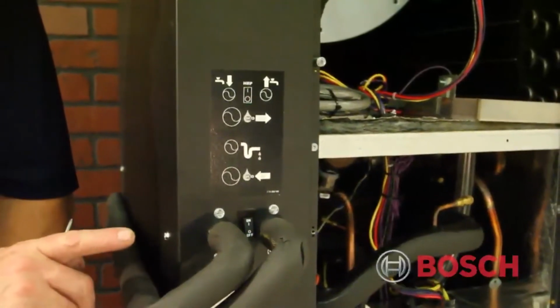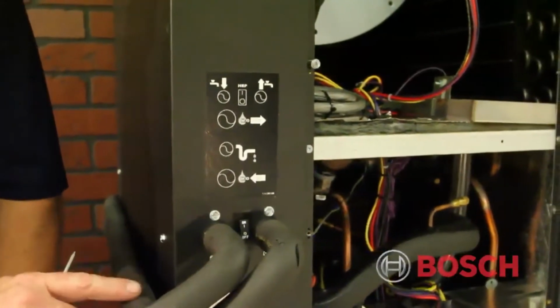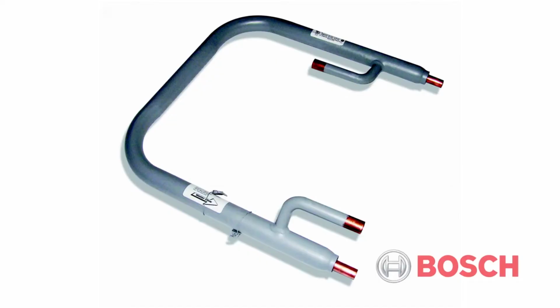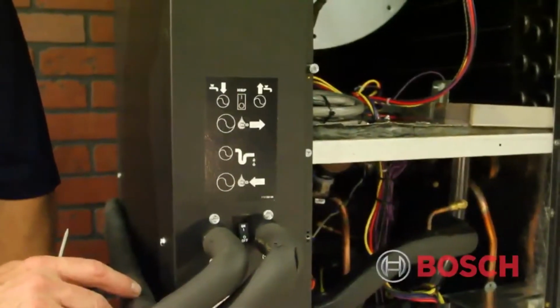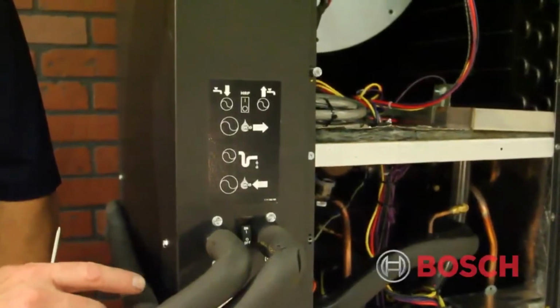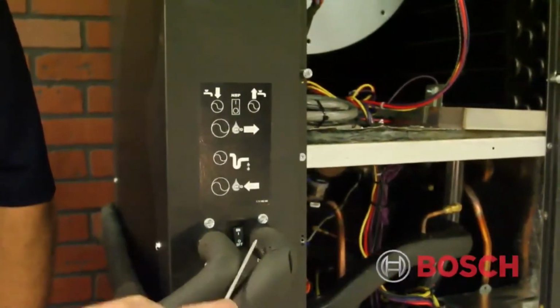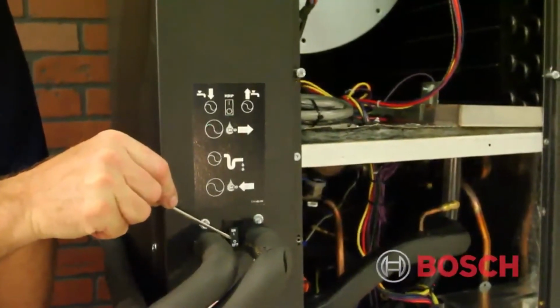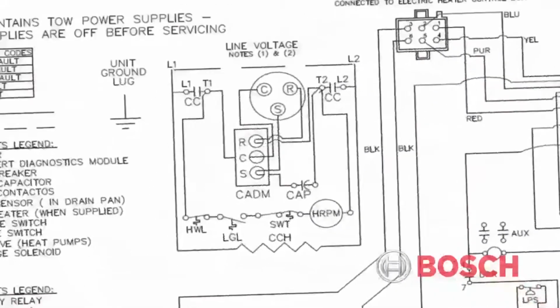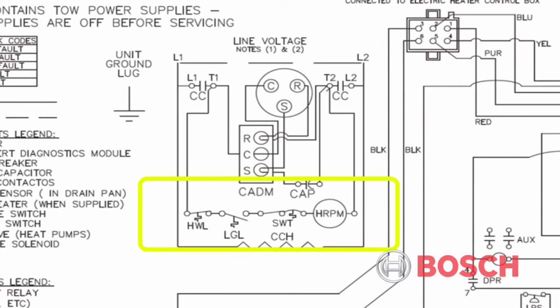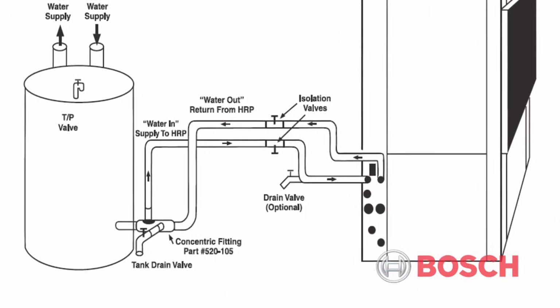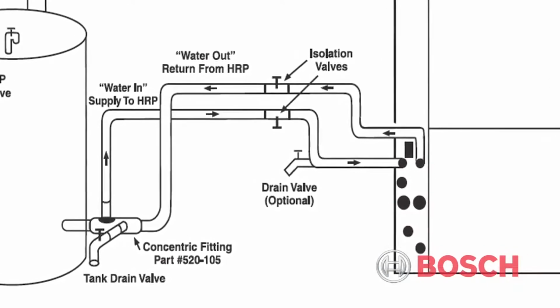The HRP heat recovery package at Bosch is a factory installed option on the Bosch TA product. Its design is to take the excess heat generated from the compressor, and through the water to refrigerant coax, the heat will be transferred to the potable water storage tank for use. The internal electrical schematic will show a 240 volt circulator, a 140 degree hot water limit, and a combination on-off 1 amp circuit breaker switch. The use of the HRP in the summertime will increase the efficiency of the equipment.